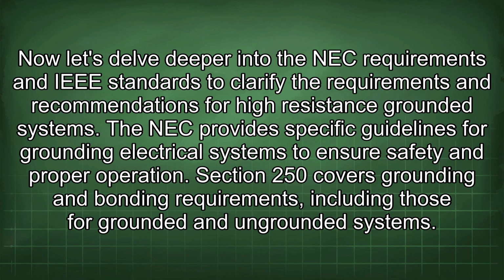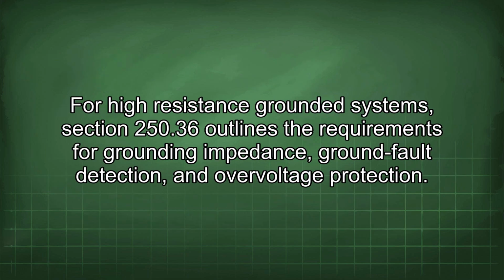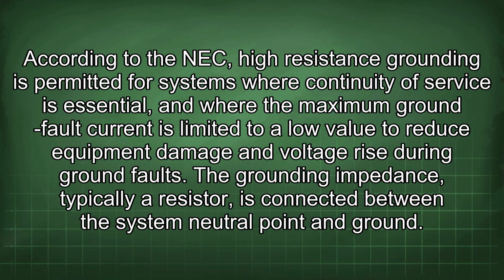Now let's delve deeper into the NEC requirements and IEEE standards to clarify the requirements and recommendations for high resistance grounded systems. The NEC provides specific guidelines for grounding electrical systems to ensure safety and proper operation. Section 250 covers grounding and bonding requirements, including those for grounded and ungrounded systems. For high-resistance grounded systems, Section 250.36 outlines the requirements for grounding impedance, ground fault detection, and overvoltage protection. According to the NEC, high-resistance grounding is permitted for systems where continuity of service is essential, and where the maximum ground fault current is limited to a low value to reduce equipment damage and voltage rise during ground faults.